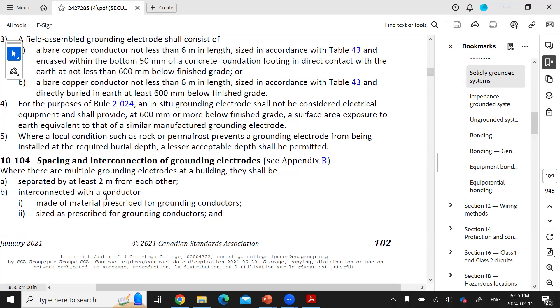This is important because the advantage of having more than one electrode is definitely realized only when they're spaced two meters apart. Because a grounding electrode requires a minimum of one meter of radial space around it for dissipation of any electrical potential into the Earth.